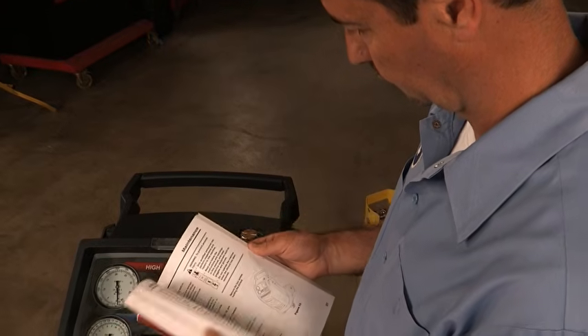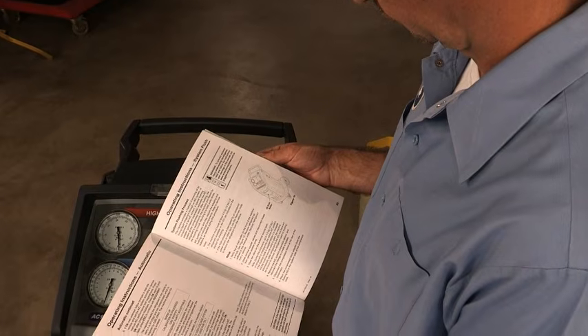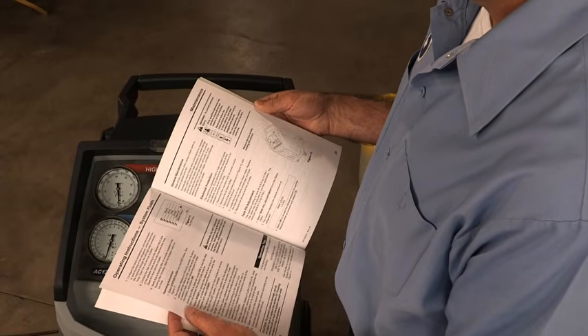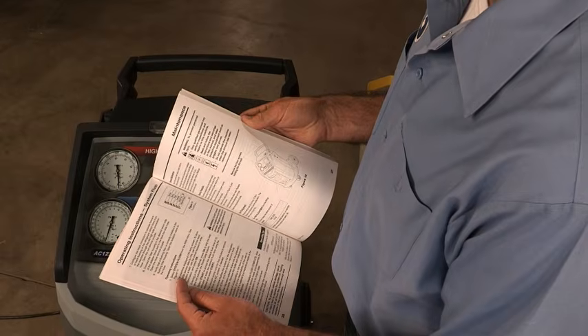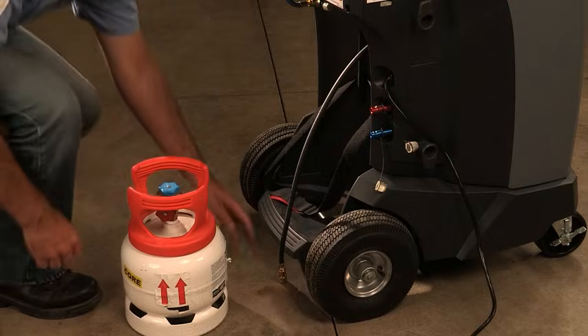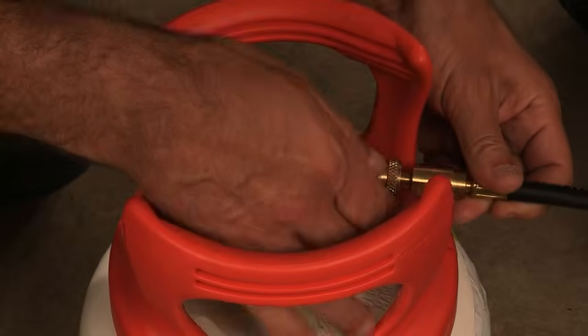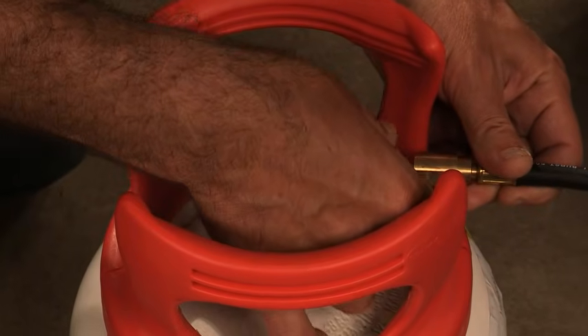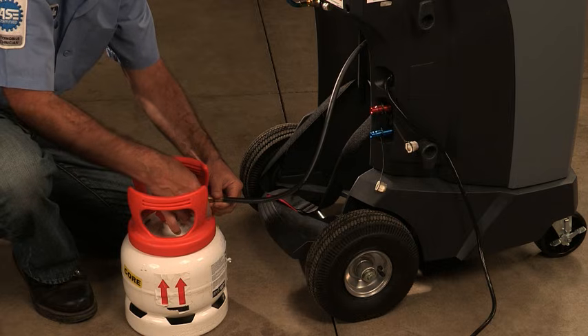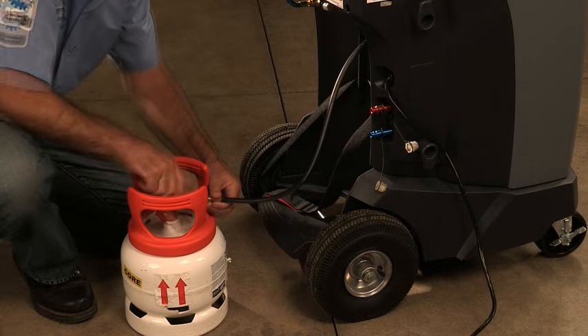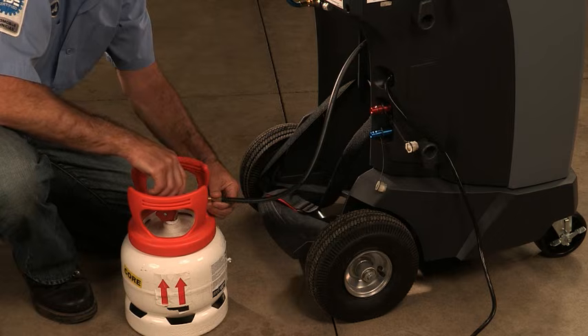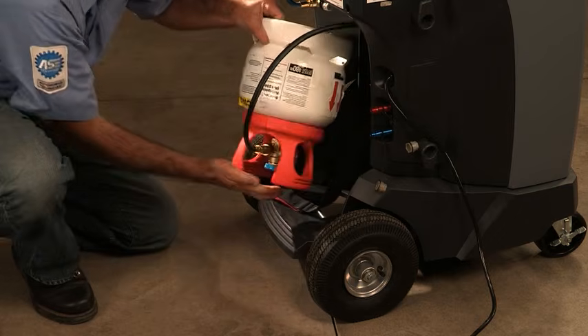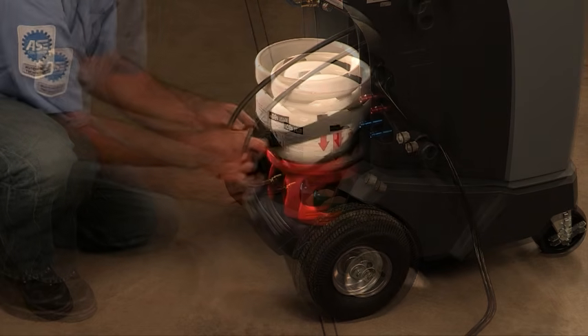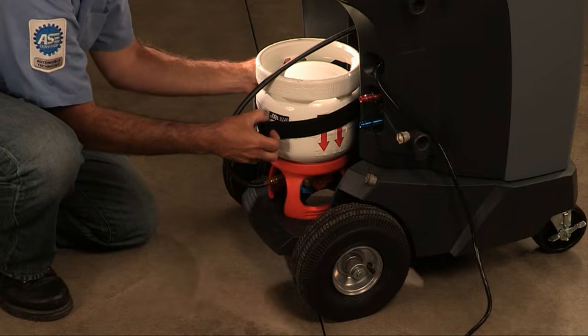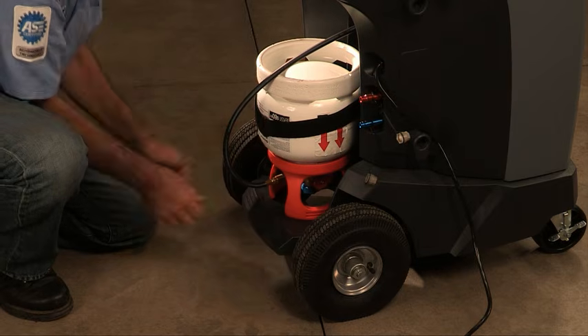The internal storage vessel, or ISV maximum fill adjustment, may be adjusted between 1.8 kilograms and 6.8 kilograms by using the keypad to make adjustments. Connect the tank fill hose to the source tank fitting and open the tank valve. In order to refill the internal storage tank, you need to position the source tank on the rear of the machine so that the liquid refrigerant is supplied to the connection. Use the strap shown here to secure the tank in place. Be careful not to block the airflow on the vents on the lower right side.